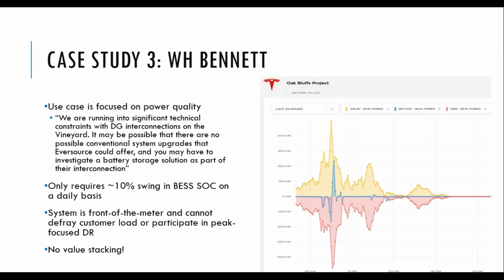What the customer was told by the EDC during the interconnection application was: 'We are running into significant technical constraints with DG interconnections on the vineyard. It may be possible that there are no conventional system upgrades, and you may have to investigate a battery storage solution as part of the interconnection.' So the goal here was really to tamp down on voltage flicker because of the relatively large amount of PV on this line and relatively small amount of customer load. There was a lot of voltage flicker the line was experiencing, especially when clouds would pass through and the PV export rate would ramp too quickly.